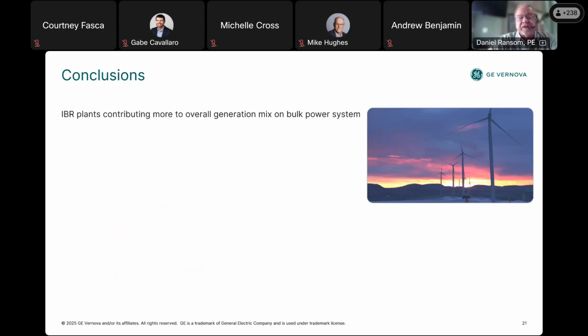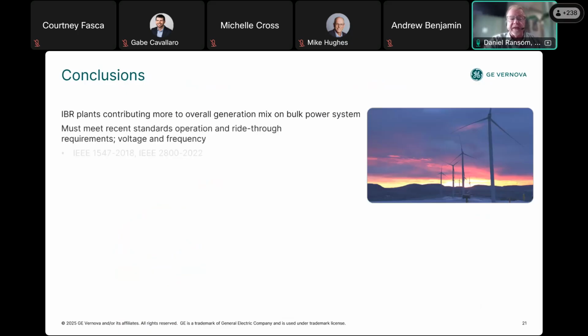Well, what we've seen here in the presentation is that inverter-based resources are contributing more to the overall generation mix of the bulk power system. Recent grid codes and standards like IEEE 1547-2018, 2800-2022, PRC-029-1 and PRC-024-3 have mandatory operation and ride-through for both voltage and frequency excursions from nominal.